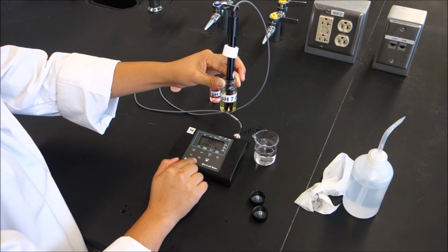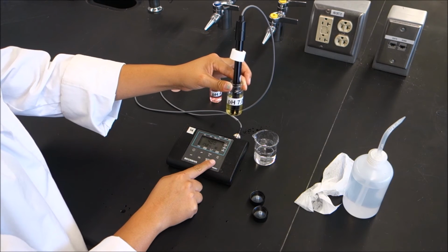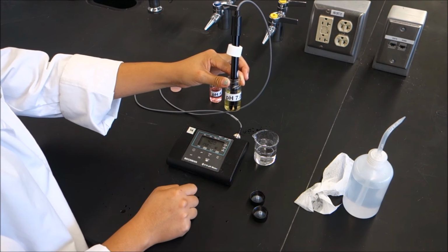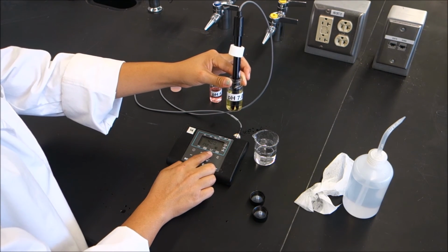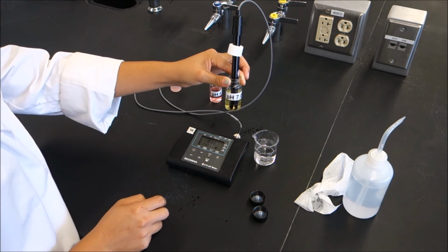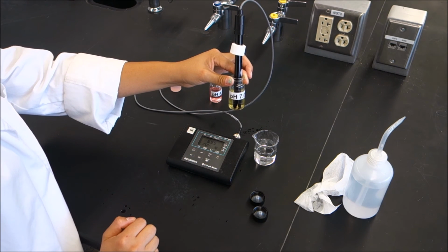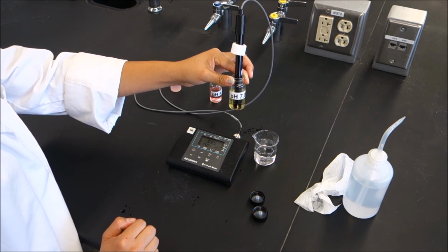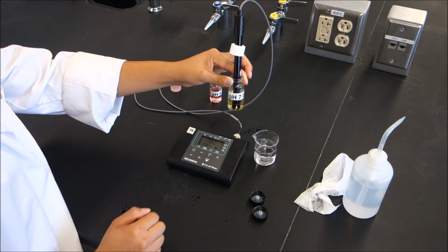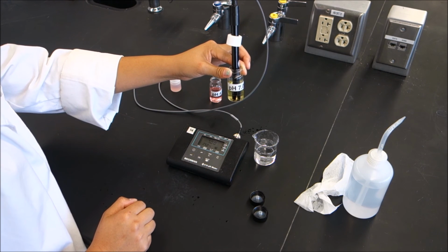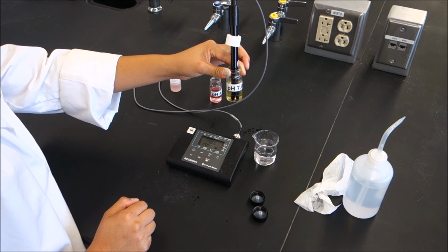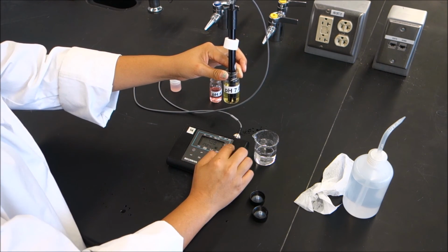That's good. And you're going to hit standard. Now don't hit clear, because you'll clear your last calibration. We just go ahead and hit standard. And it's going to blink where it says standard 2. And it'll read 7. Now, to double check that both of your standards are calibrated, you can look here.